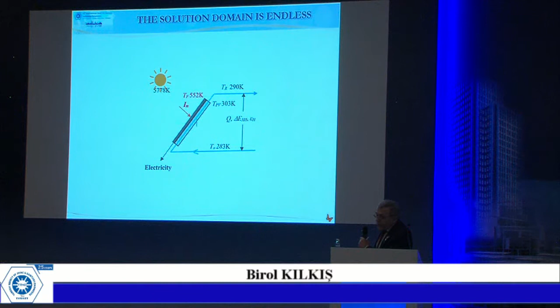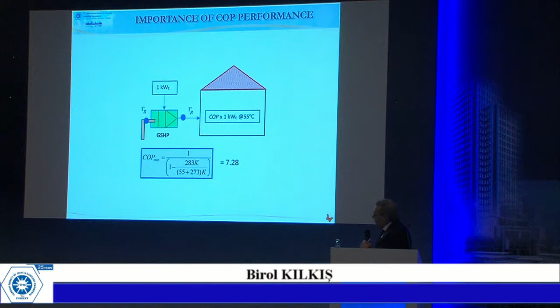Well, heat pump—again, for a heat pump getting as output 55 degrees Celsius heat at 1 kilowatt of electricity, your COP minimum must again be 7.2 to become even. And as you see, the exergy-based COP is less than 1, although your COP is enjoying numbers like 5. Your exergy-based COP, which actually compares what you get in quality terms and what you put in quality terms, is less than 1. You're at a loss.